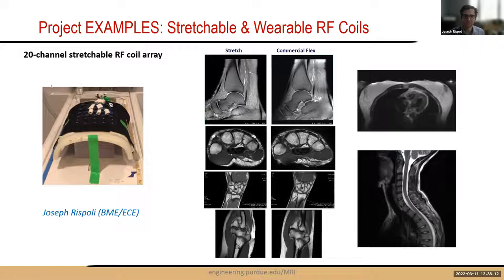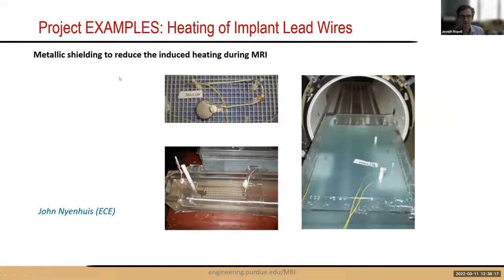Another hardware project from Professor John Nyenhuis (professor emeritus of electrical engineering) investigates induced heating during MRI from wires in medical implants, specifically pacemaker lead wires, examining whether metallic shielding can reduce heating. An industry-standard large phantom is used for evaluating heating during scans. The facility also has spectroscopy phantoms and imaging phantoms useful for protocol development before human subjects research.